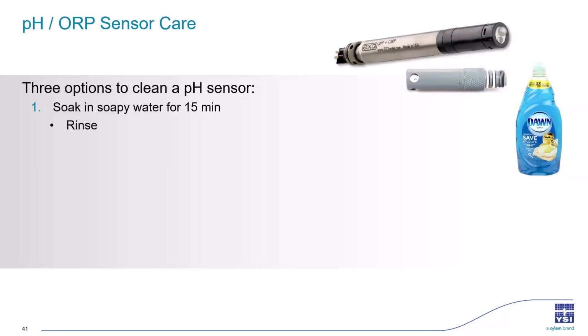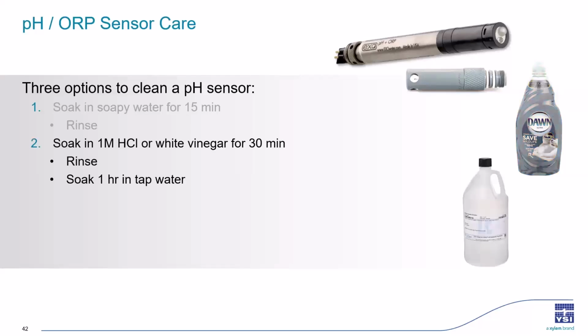Starting with pH and ORP sensor care, there's going to be 3 options of cleaning a pH sensor depending on how dirty it is and what kind of fouling you're seeing. So if you're just needing to clean off some light dirt and debris, you can soak the sensor in tap water with a drop of dish soap, swish it around, and then rinse it off really well with clean tap water. So that's one way.